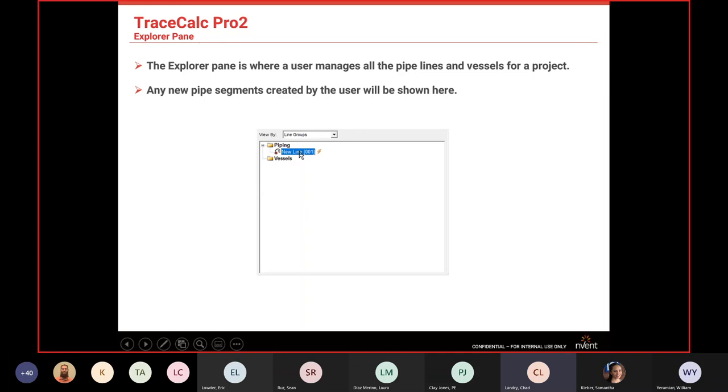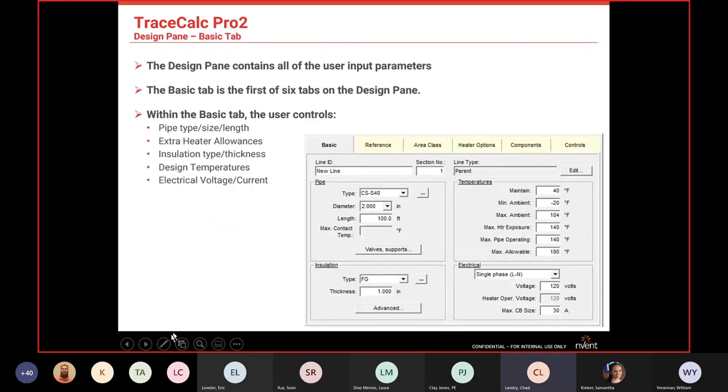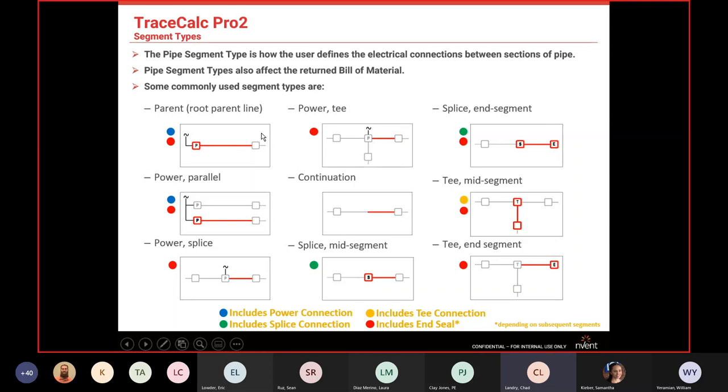In the explorer pane, this is where we're going to build our piping. You can create new lines and segments. When building circuits in TraceCalc, there are root circuits, power-in-parallel options for instruments on the same circuit, and power splices. The interface is color-coded — a blue parent line generates a full bill of material with power box, cable type, and end seal. Power-parallel connections include power connections and end seal in the bill of material.